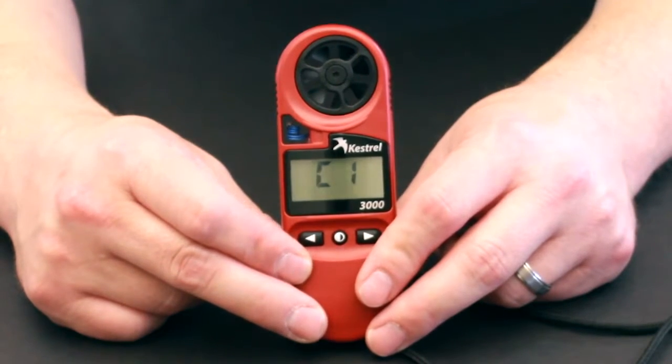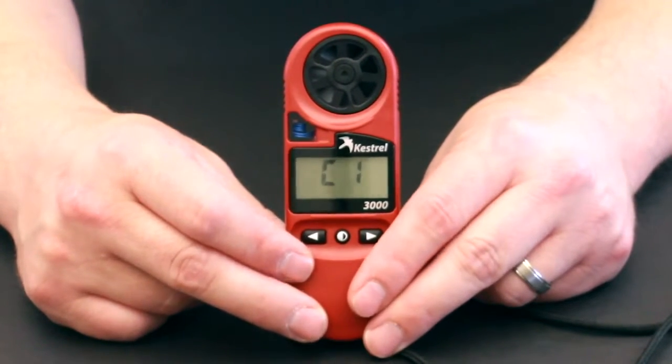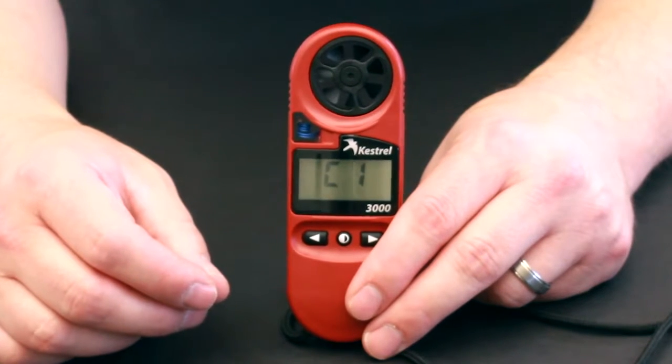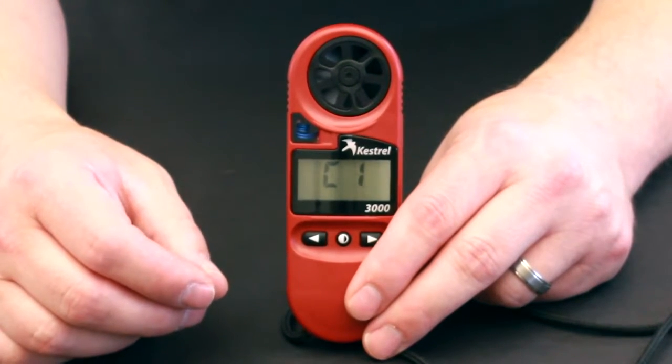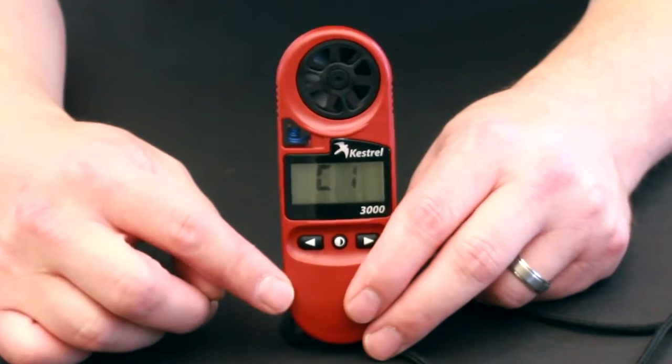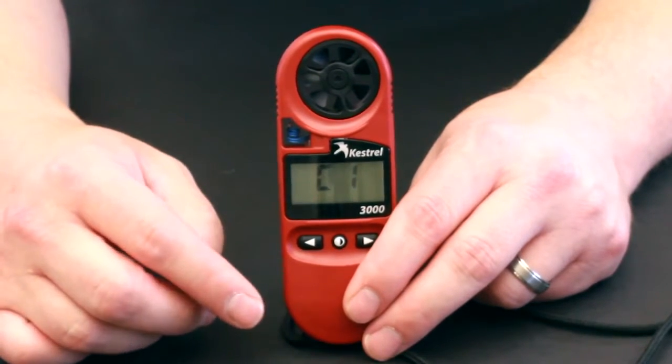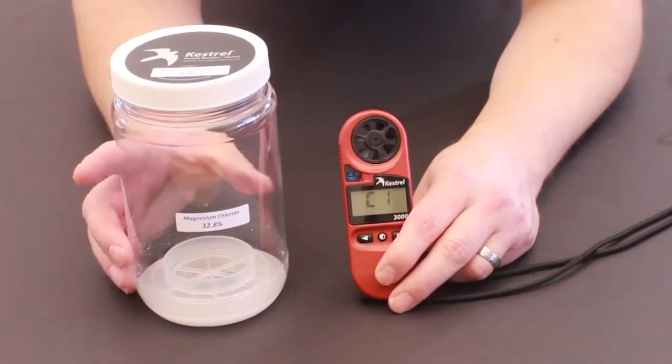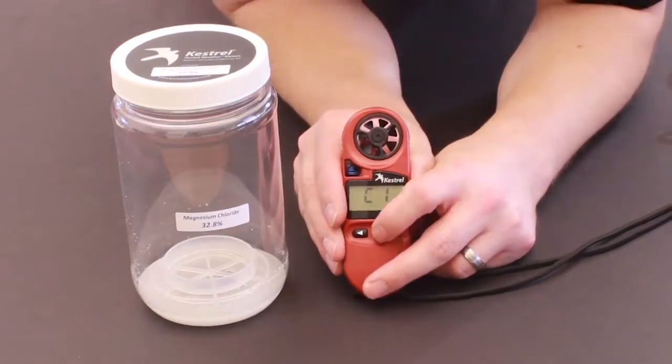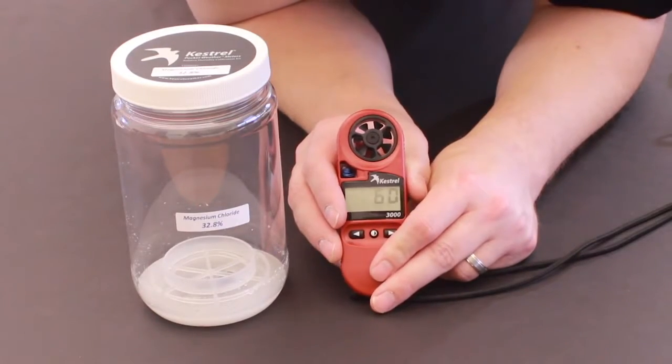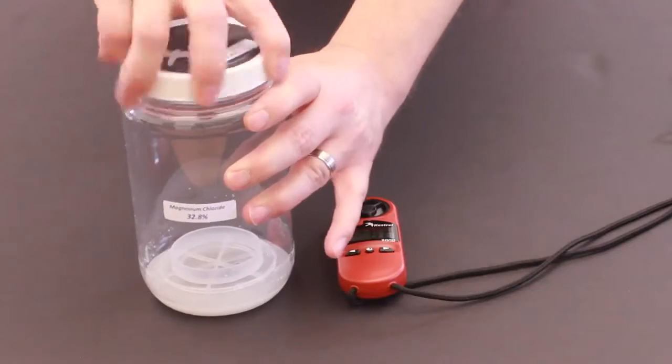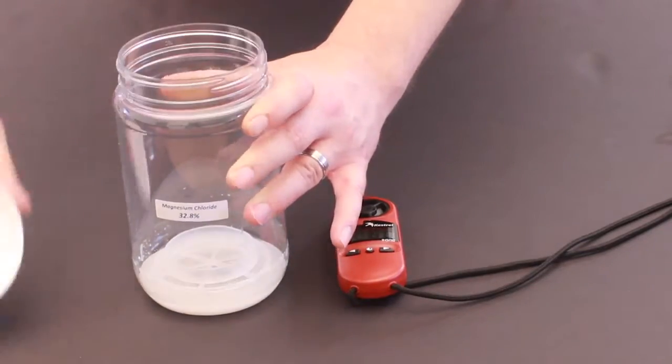Once we hit the center button, we're going to have to put this unit upside down into the first chamber, which is the magnesium chloride chamber. Please note, if you have a two-button Kestrel, the instructions tell you to do these in the reverse order. Once we get the magnesium chloride chamber, we're going to hit the center button and you'll start seeing it flash C1 and 60. This means that it's going to go for 60 minutes in this magnesium chloride chamber.